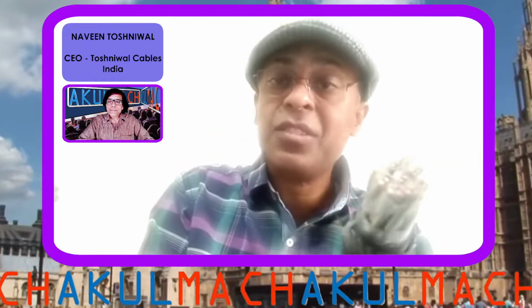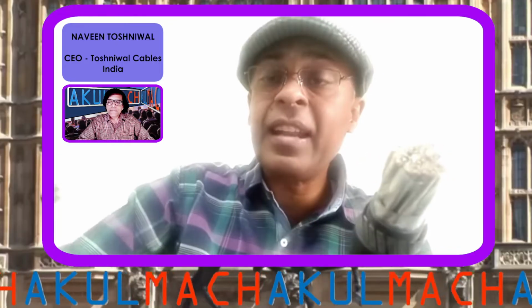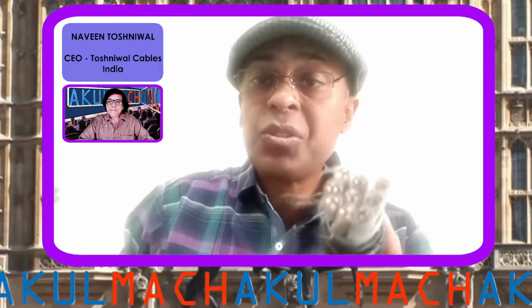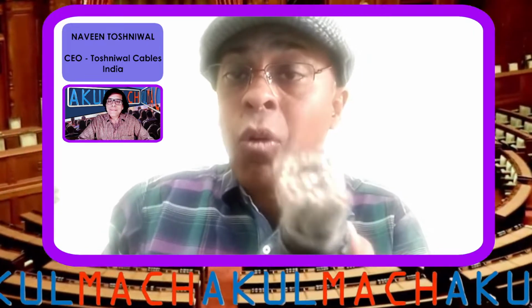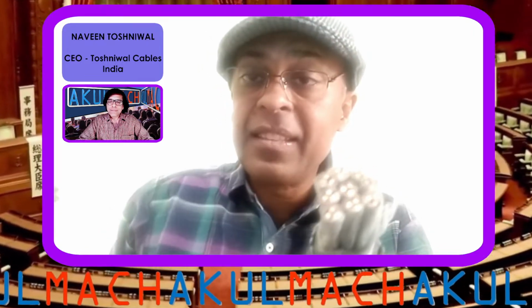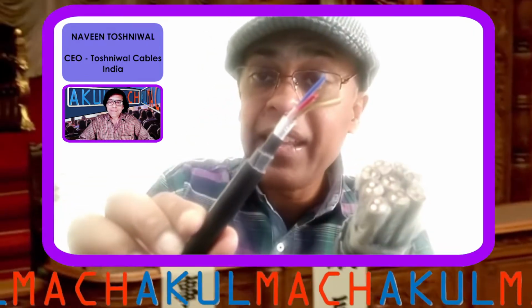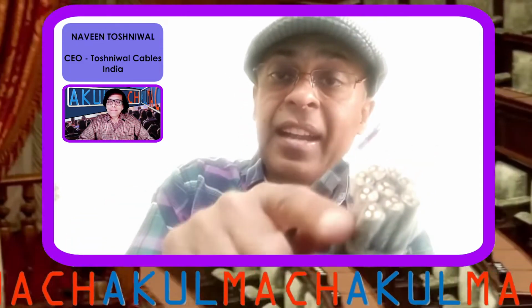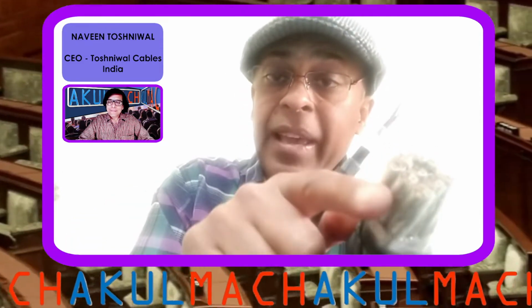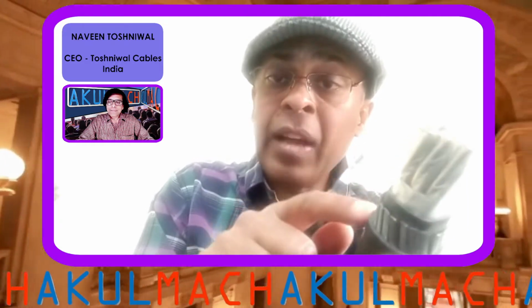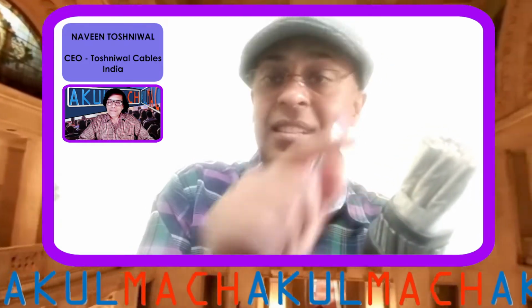So this is as per the relevant Indian and international standards. So this will give you an idea of how a multi-triad cable looks like. This is a single triad RTD cable, and this is a multi-triad RTD cable with each pair overall shielding and also an armor for mechanical protection.